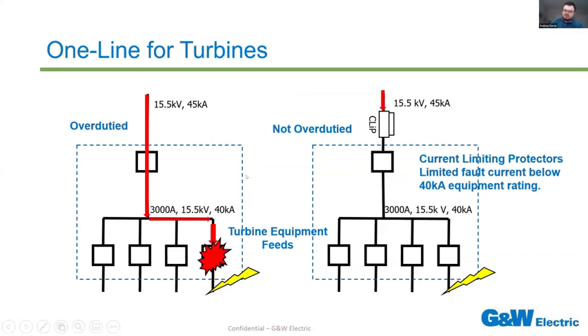Pretty simple setup. You have your over duty scenario, say 45K fault current available, and downstream equipment only rated for 40K. Then you could put a current limiting device such as a clip in there. It could be any current limiting device. You could use a reactor or an appropriately sized solid state breaker or fuse in there to intercept that fault current and limit it to below that 40K level.